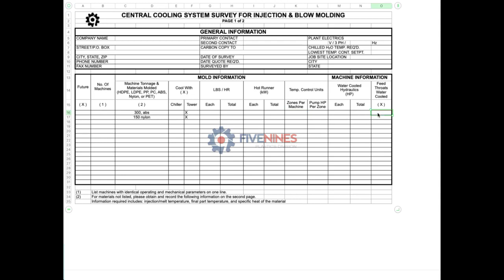And then a question that comes up fairly often is: okay, it's all well and good to understand what the cooling load requirements are from a machine equipment perspective. However, how do we manage or understand flow, pressure, sizes of channels, number of elbows, all that kind of thing? Because some have very different configurations, and it's helpful to understand how that may or may not be affecting the overall performance of the system, because we all want turbulent flow.